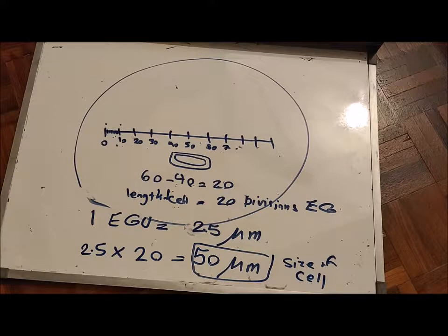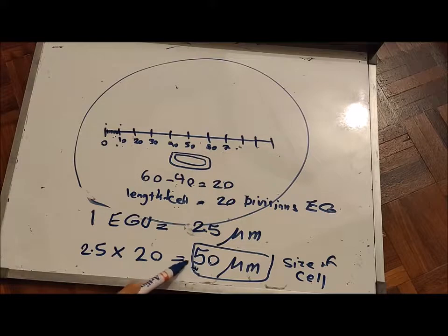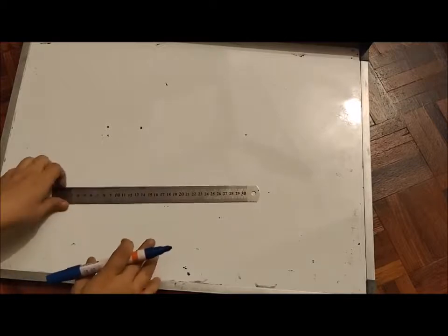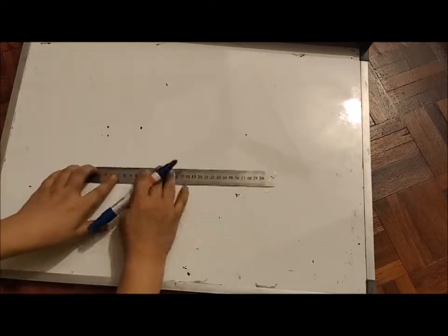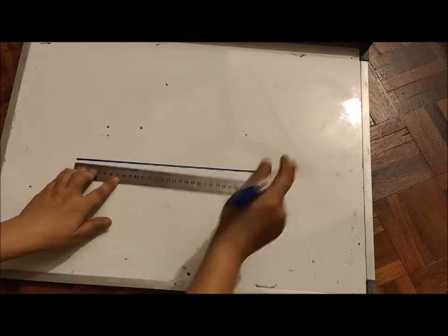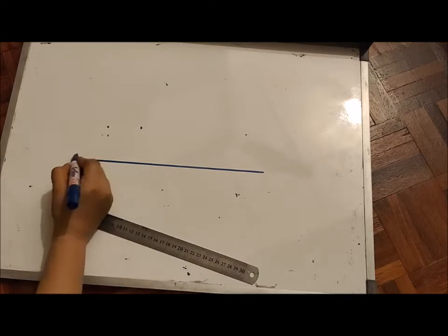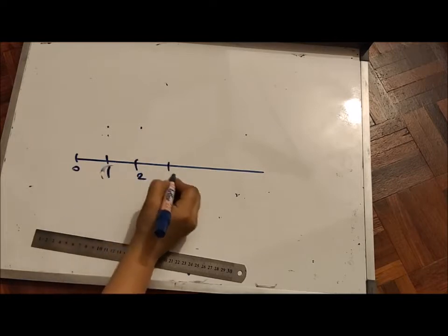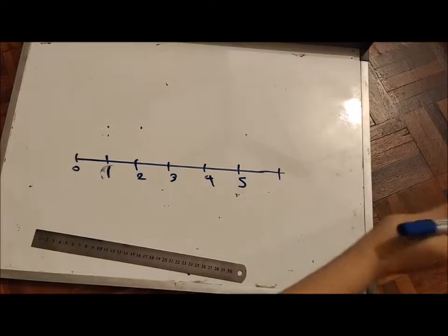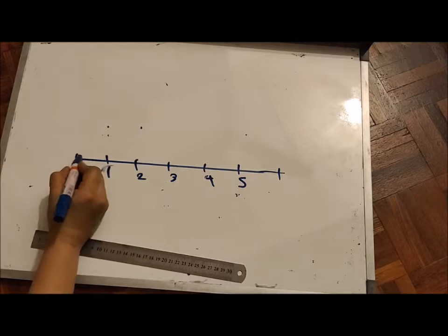So what is the stage micrometer? It's exactly like a ruler, but it has no proper units — no centimeters, no meters — and that's what you have to find out. Imagine we have a stage micrometer like this. It is bigger and it also has 100 divisions: 1, 2, 3, 4, 5, 6, 7, 8, 9, 10 — and between each of those you have another 10 divisions.